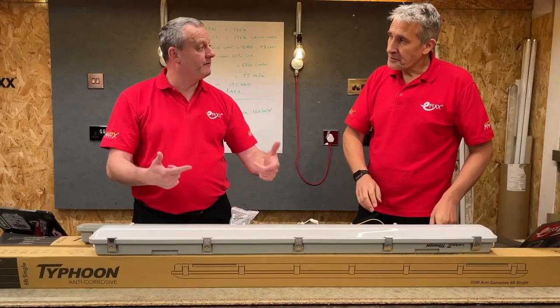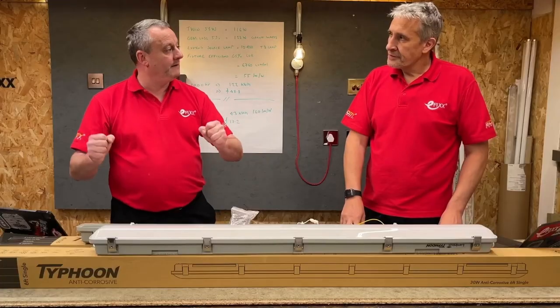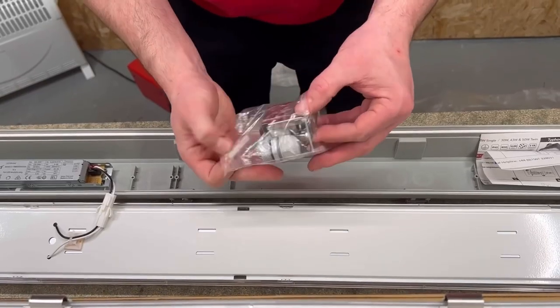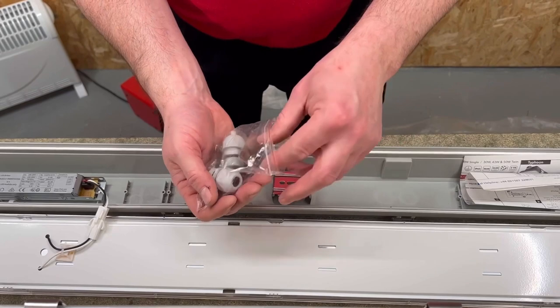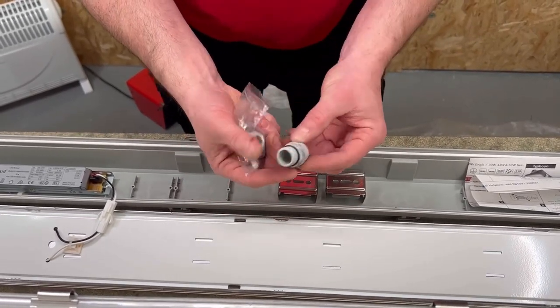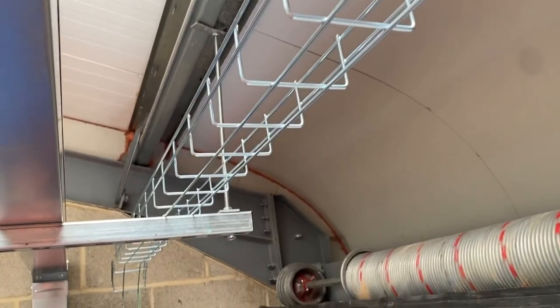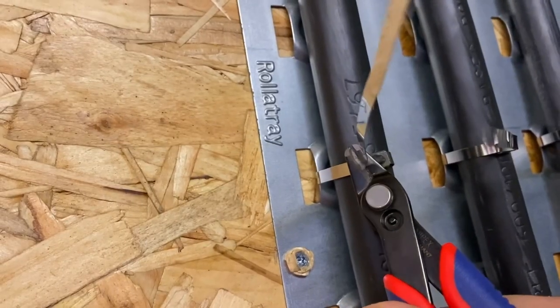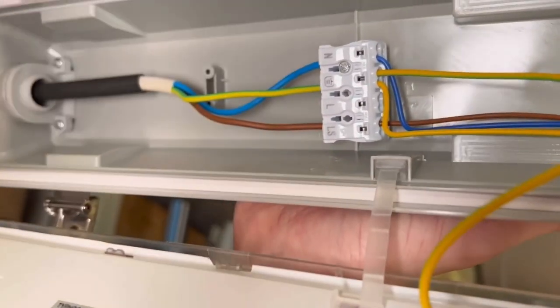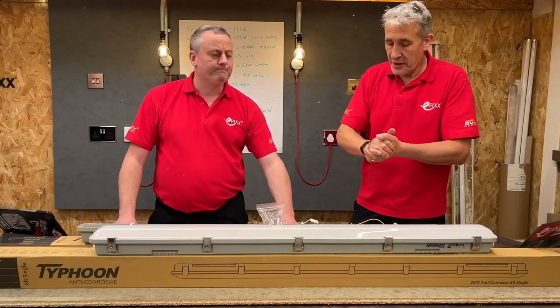It's the first time I've had a fitting with that threaded insert — it was so easy. The gland's already got a little O-ring on it; the gland goes in and it's fitting itself really. Not using the armoured cable meant you could use the supplied glands that come in a little accessory pack — and there are two of them as well, which is good. It's that massive debate though — we put armoured cables in loads of locations that never get interfered with: ladder racking, cable tray, basket, maybe even roller tray. What actually ever gets near it? Another feature I like is the additional terminal in there that you can loop through, even if this version isn't an emergency fitting.